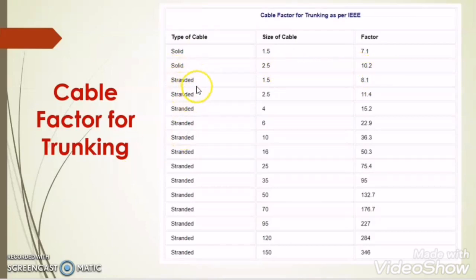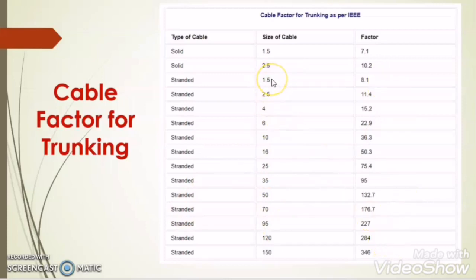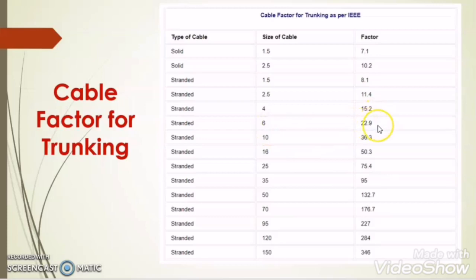In the same way, for stranded type wires or cables of different sizes, there are factors mentioned in this table. For 1.5mm stranded cable, the factor is 8.1. For 2.5mm, the factor is 11.4. For 4mm, 15.2. For 6mm, 22.9. Likewise, for 150 sq mm, the factor is 346.